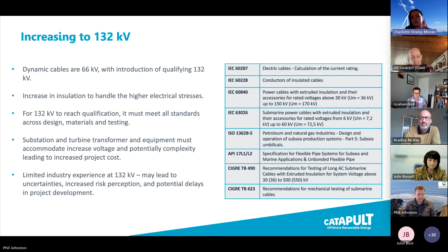There's a lot of opportunity in moving to 132 kV, and as we look to higher capacity turbines, we'll need to start adjusting to higher voltage levels in our cables. With careful planning and upkeep of corresponding standards, there's a lot of potential in 132 kV, including critical consideration of expansion toward higher capacity turbines. Another benefit of tackling this earlier is supporting supply chain readiness and mitigating bottlenecks at an early stage, such as standards and available equipment, pushing through these technical barriers. If you jump to the next slide, please, Phil.